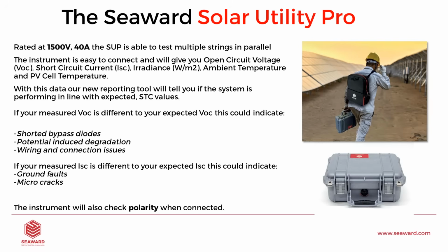We then take this data and import it into our reporting tool, and this will tell you if the system is performing in line with our expected standard test condition values. So for instance, if your measured VOC is different to your expected VOC, this could indicate that we have shorted bypass diodes, PID, wiring and connection issues. And also, if your measured short circuit current is different to your expected ISC, this could indicate that we have ground faults or micro cracks, or perhaps a combination of faults.